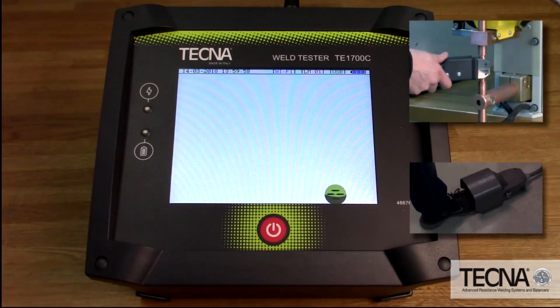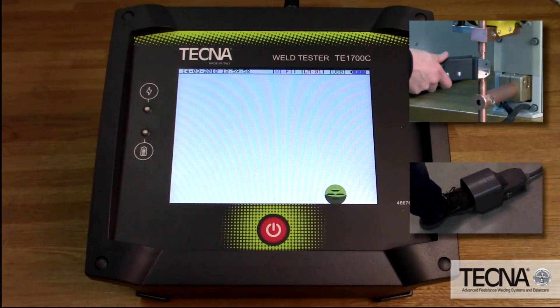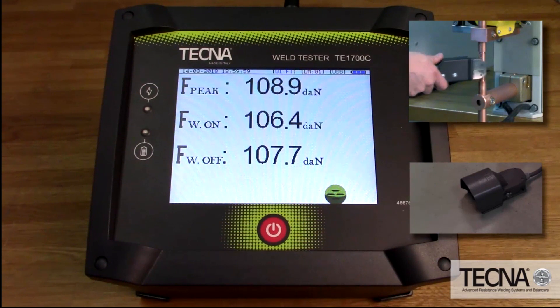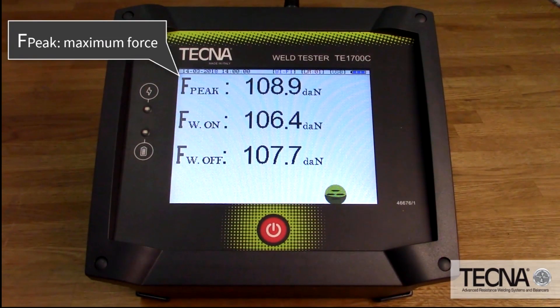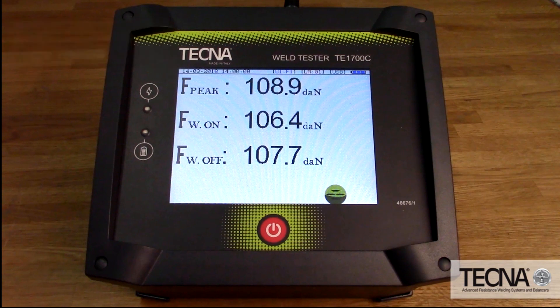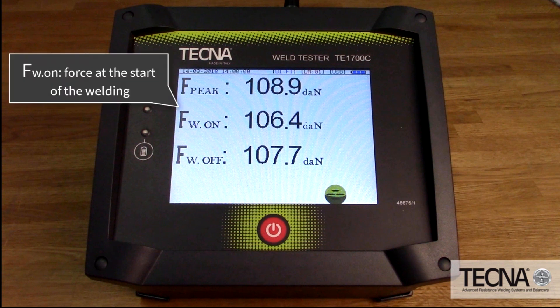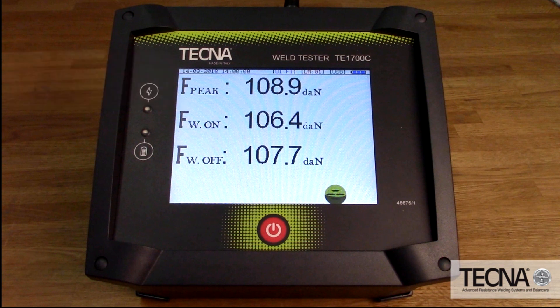The TE1700C can be used as confirmation that proper weld force has been developed prior to passing weld current. Firing before proper weld force has been developed can lead to poor or inconsistent weld quality. You can use the FW ON and FW OFF to ensure proper weld force was met prior to and at the end of the weld time.